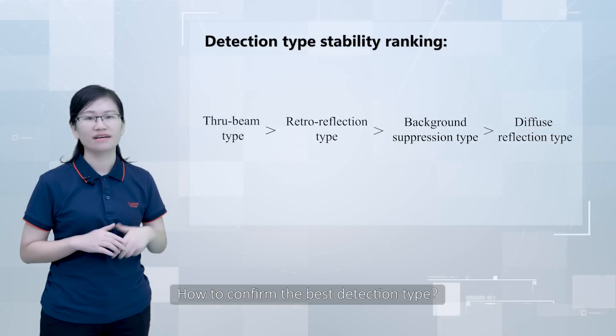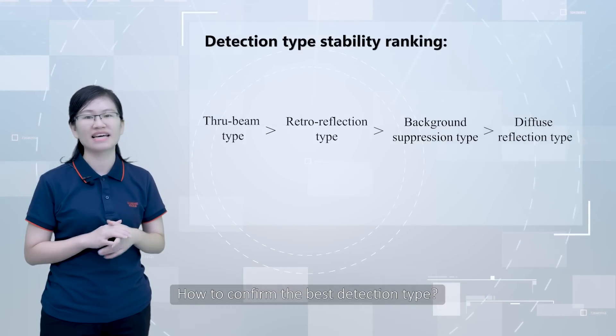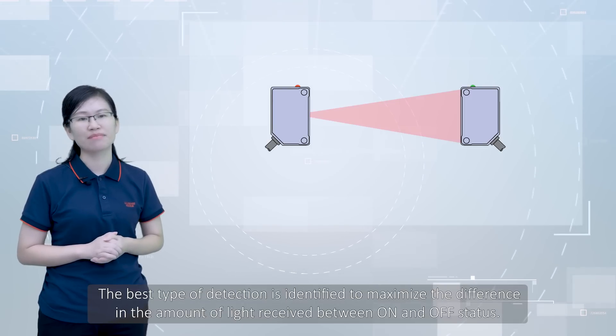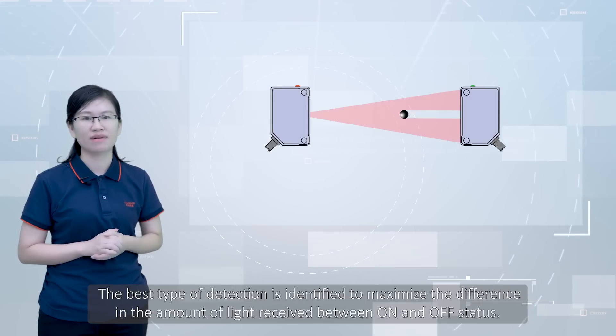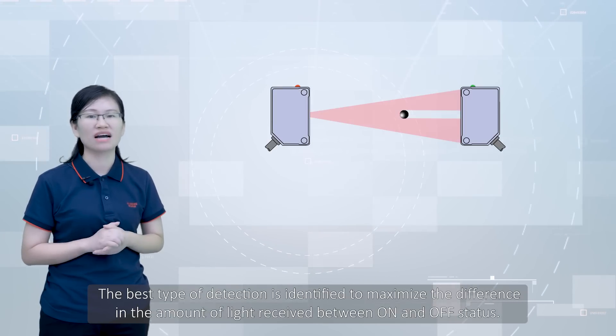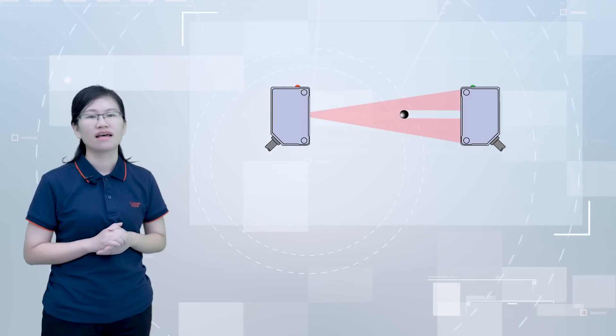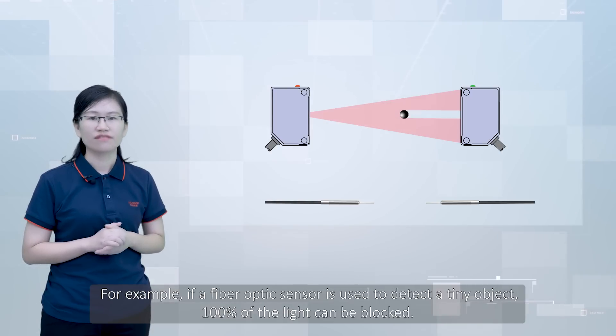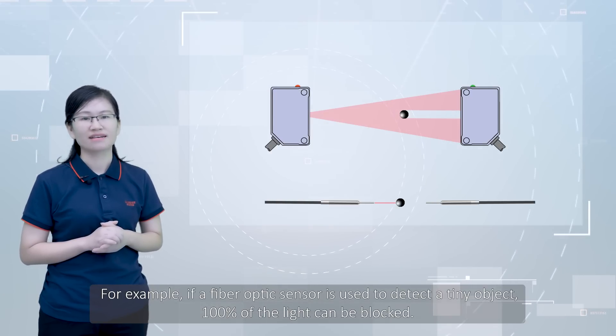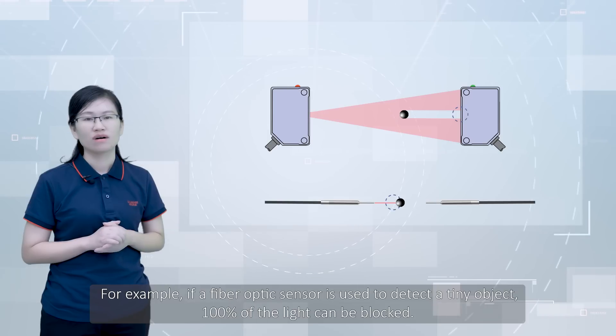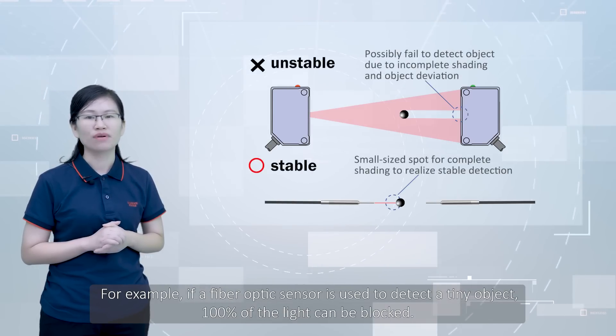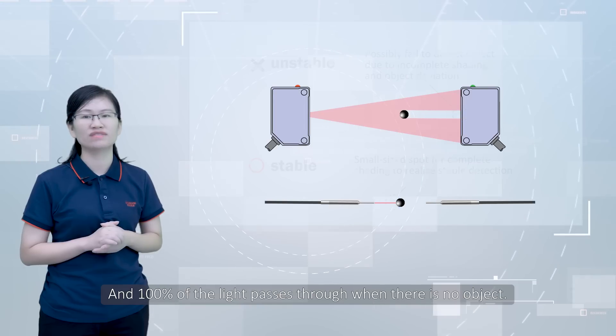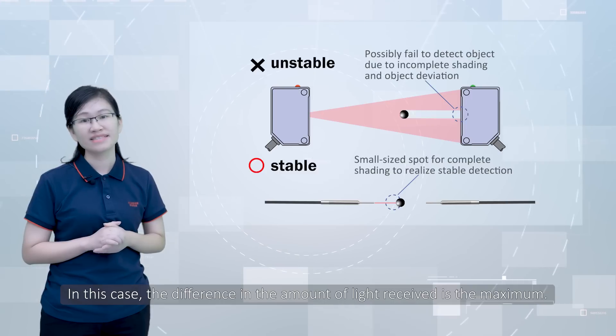How to confirm the best detection type? The best type of detection is identified to maximize the difference in the amount of light received between on and off status. For example, if a fiber optic sensor is used to detect a tiny object, 100% of the light can be blocked and 100% of the light passes through when there is no object. In this case, the difference in the amount of light received is the maximum.